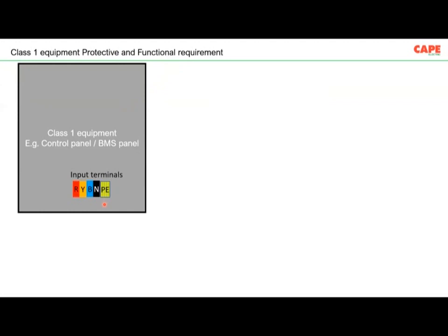Control panels, which have, for example, a 24-volt PLC or some kind of communication equipment, are supposed to have one more terminal, which is called the FE, functional earthing terminal. In an electrical installation, the functional earthing and the protective earthing must be connected strictly only at one place, not at frequent places. So functional earthing is basically called an isolated earthing or an insulated earthing.